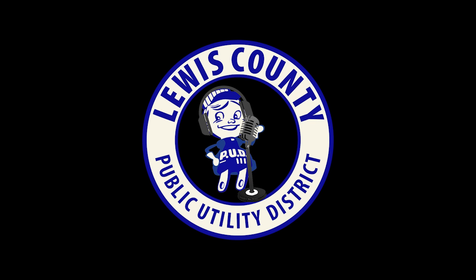Right now, if you see a line on the ground, treat it like it's live, because it could be. Faults are hard to detect, it's kind of an art and science at the same time. We try to capture every single fault, but sometimes the device just sees it like someone turned on a lot of load at once, and it doesn't look like a fault to that relay. So it sits there and doesn't open up, and that's when you have wires on the ground.